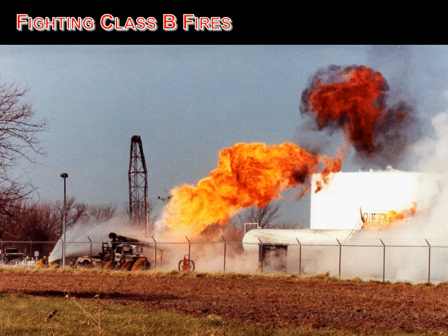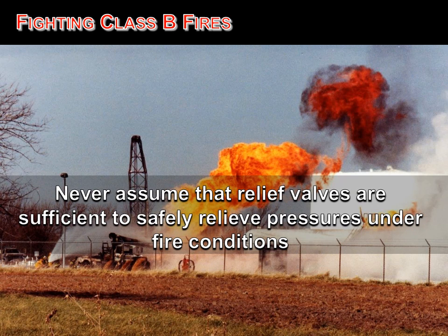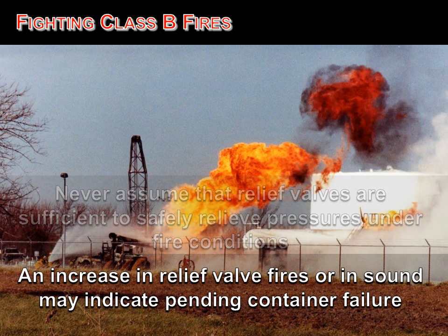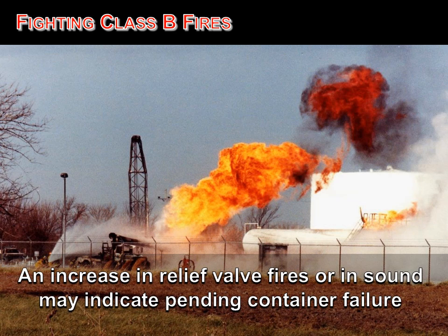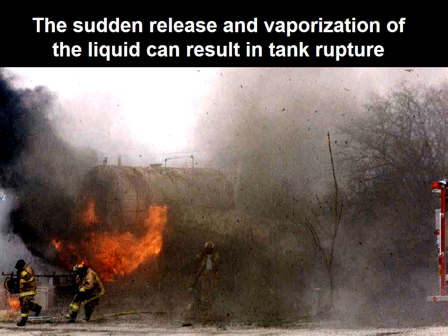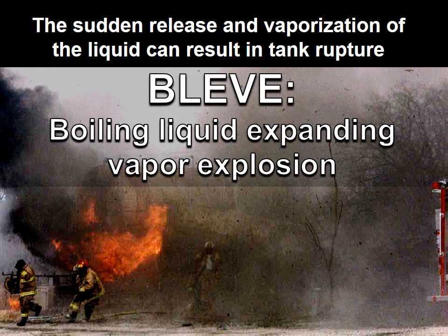Unless the leaking product can be turned off, fires burning around the relief valves or piping should not be extinguished. Never assume that relief valves are sufficient to safely relieve pressures under fire conditions. An increase in relief valve fires or in sound may indicate failure. The sudden release of vaporized liquid can result in a tank rupture.